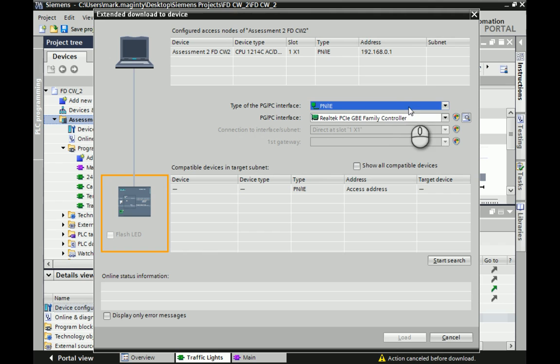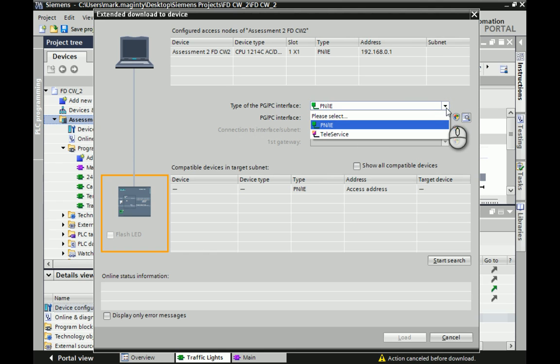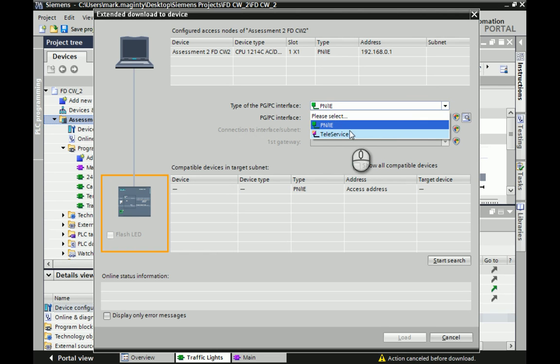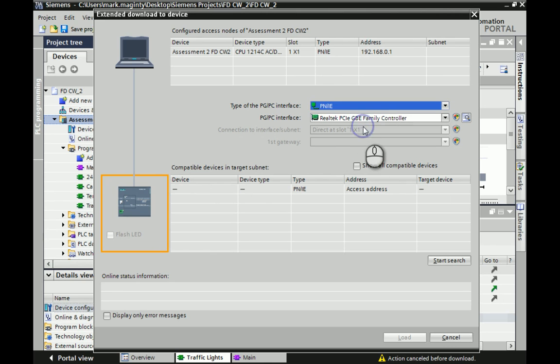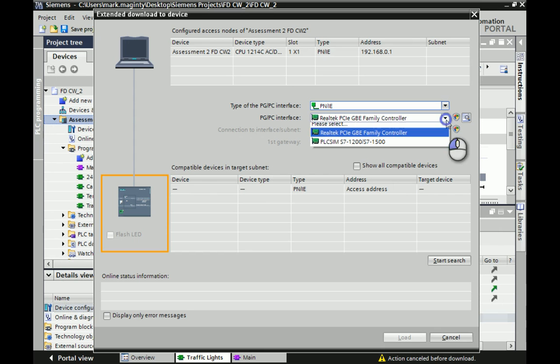What you need to select is the top options here from the drop-down menu depending on what type of equipment hardware you're connecting with. In my case, it's a desktop. I don't have built-in Wi-Fi. So I've only got two options: PNIE, which is the PROFINET for industrial Ethernet, which is your green cable from Siemens, or teleservice. The one we want is the PNIE. From that, you will then be given extra options about how you're going to connect via that particular PNIE.